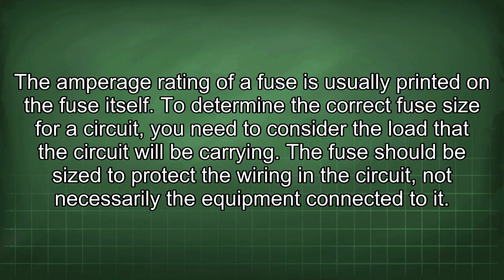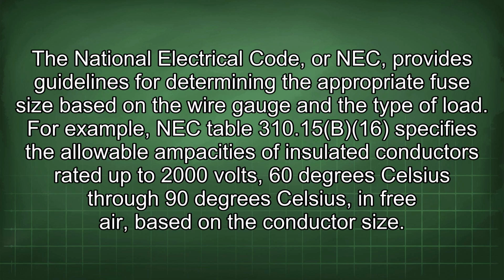To determine the correct fuse size for a circuit, you need to consider the load that the circuit will be carrying. The fuse should be sized to protect the wiring in the circuit, not necessarily the equipment connected to it. The National Electrical Code, or NEC, provides guidelines for determining the appropriate fuse size based on the wire gauge and the type of load. For example, NEC Table 310.15(B)(16) specifies the allowable ampacities of insulated conductors rated up to 2000 volts, 60 degrees Celsius through 90 degrees Celsius, in free air, based on the conductor size.